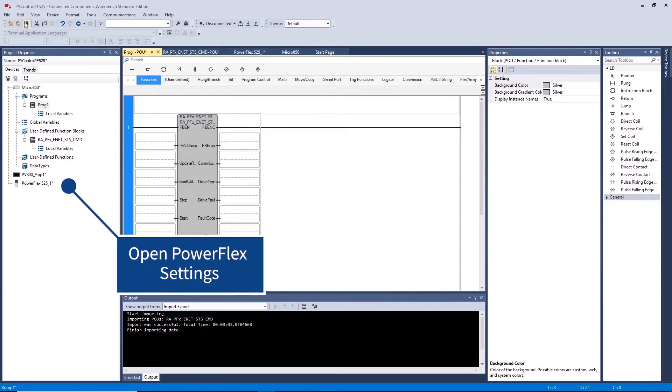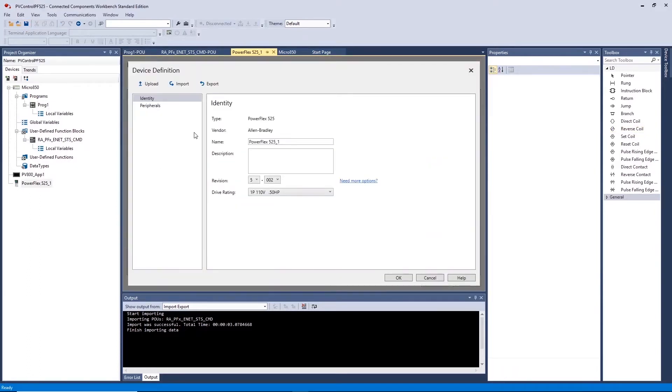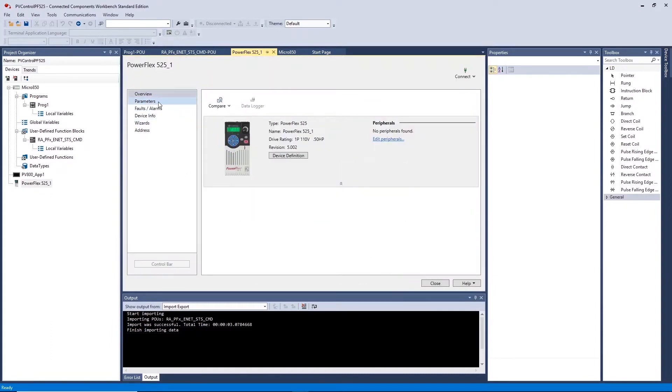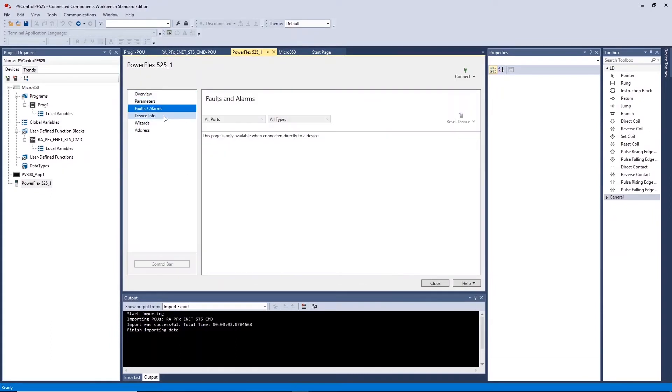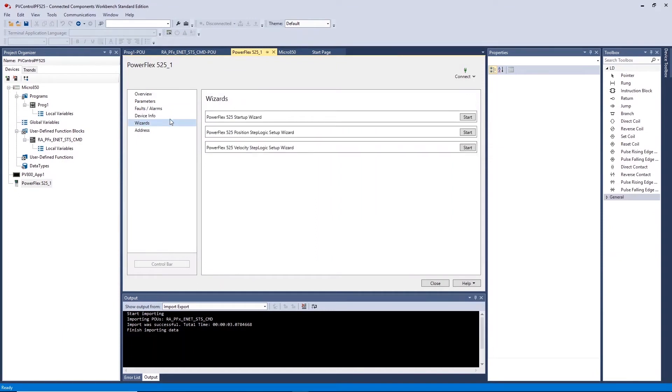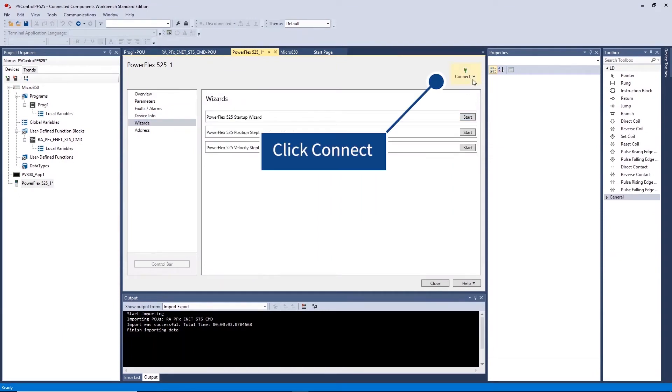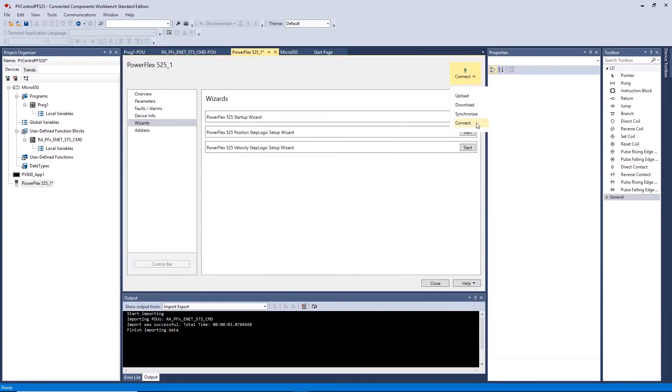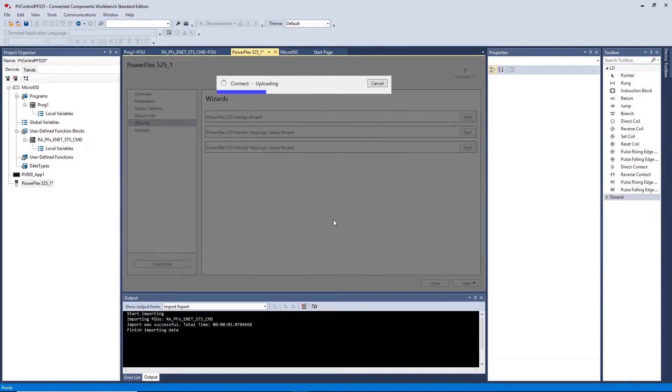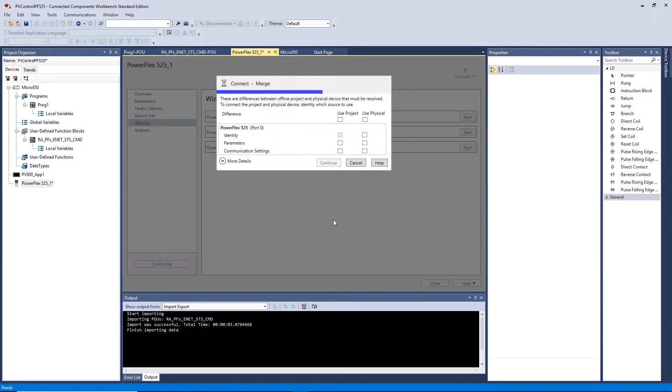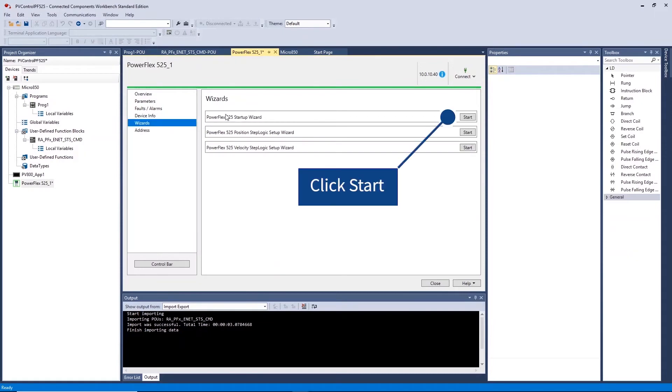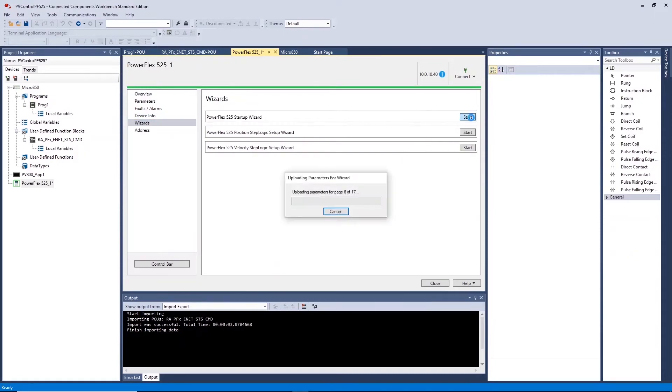Before this return to the PowerFlex 525 settings to set up the drive parameters. Wizards are an easy way to set up and configure the drive. To connect to a drive on the network click connect and select your drive. Tick use physical to obtain drive parameters if configured. Return to Wizards and begin the startup wizard to configure your drive.